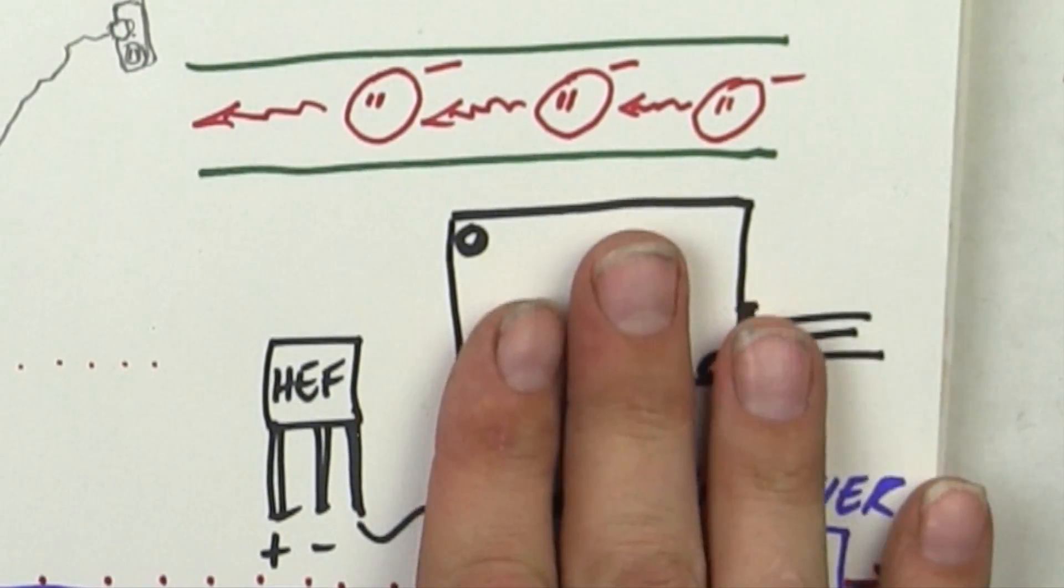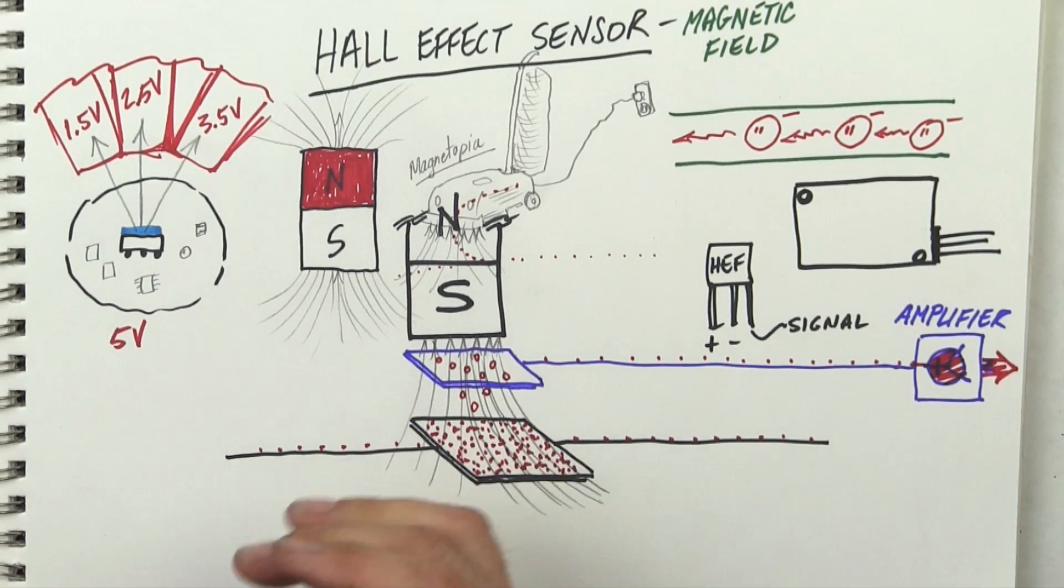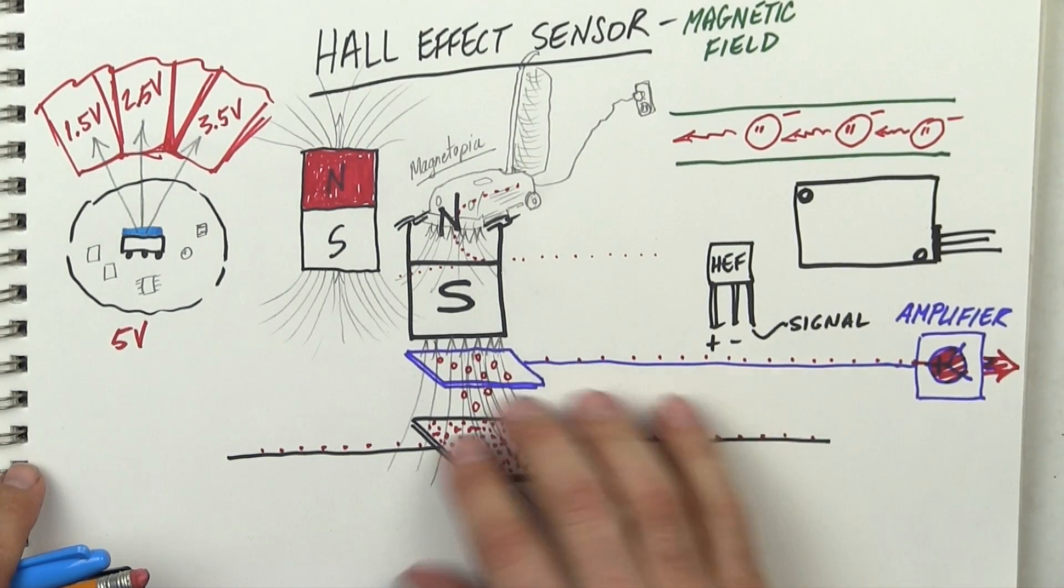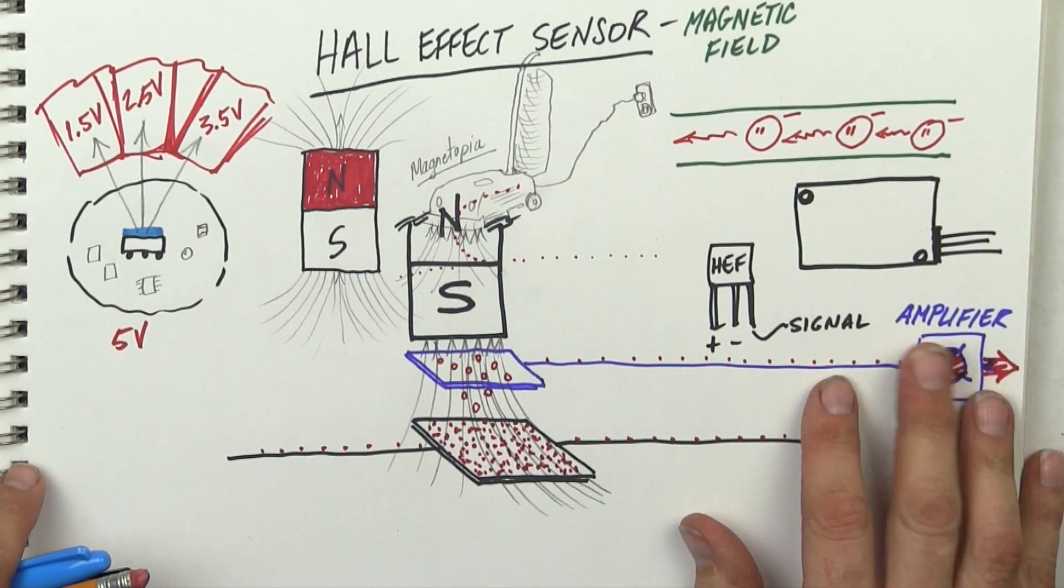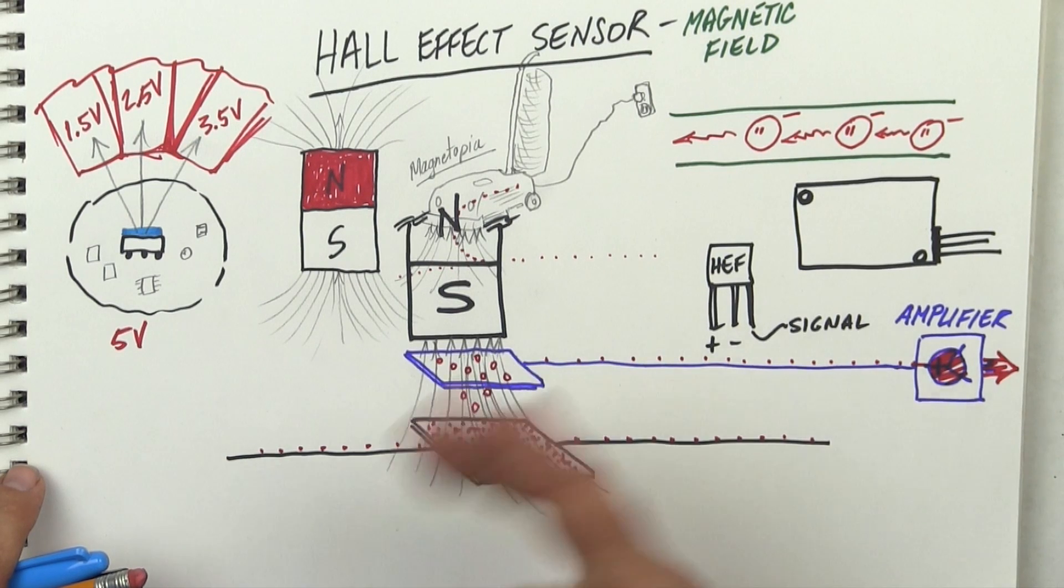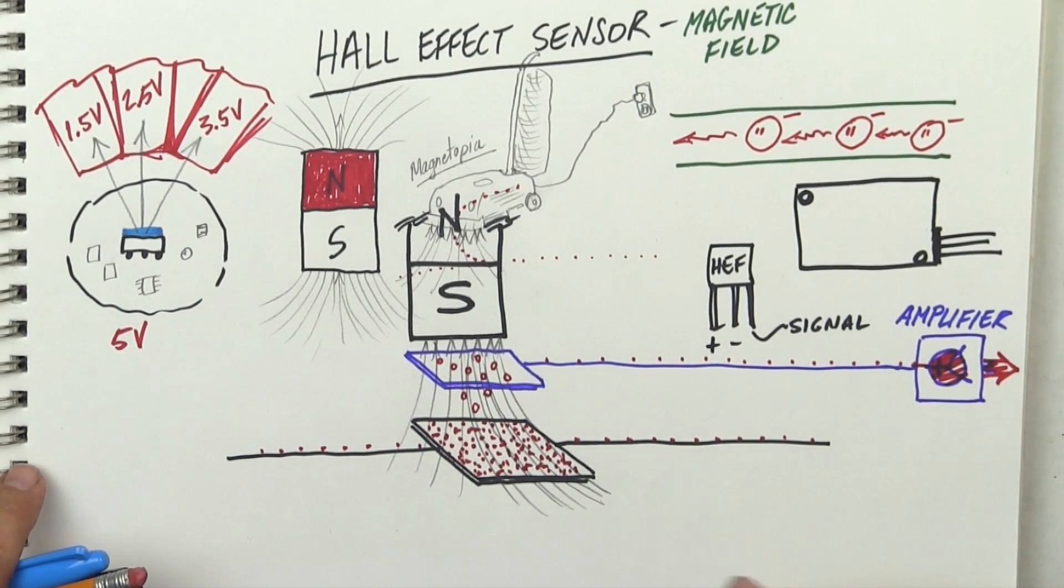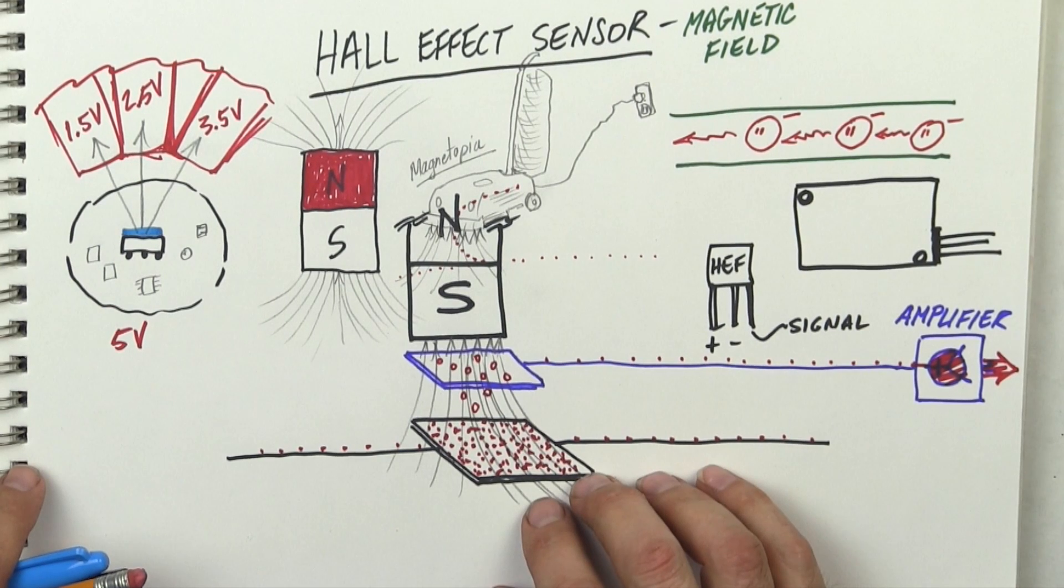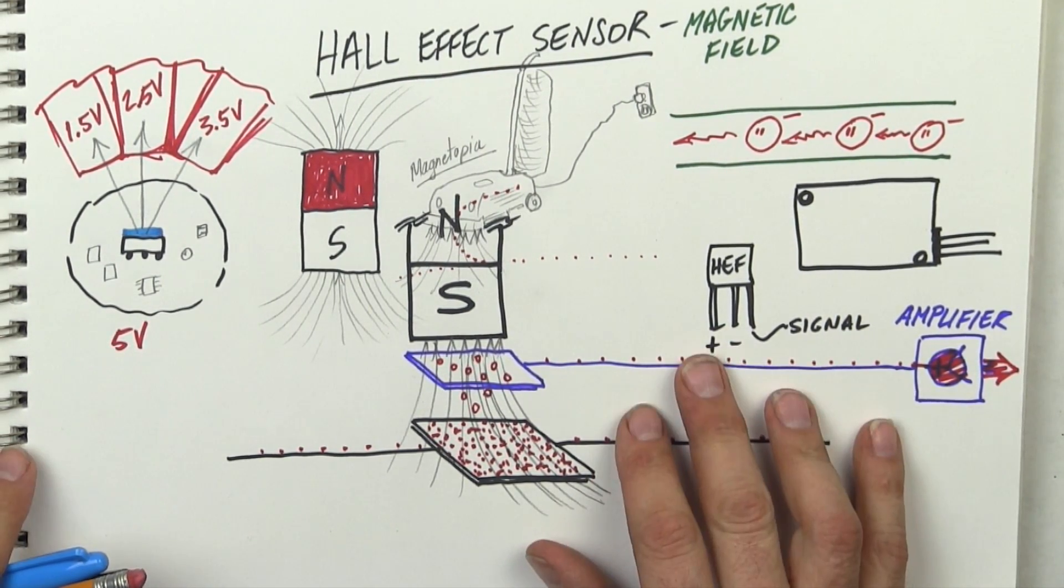The three wires to me is a dead giveaway that it's a Hall effect. If there's two wires it's going to be a switch which is referred to as a reed switch. Hall effect sensor is much more stable and much more sensitive than a reed switch is. The guy that figured out, his name was Hall obviously, and it was way back when, long time ago, 1800s or late 1800s early 1900s.